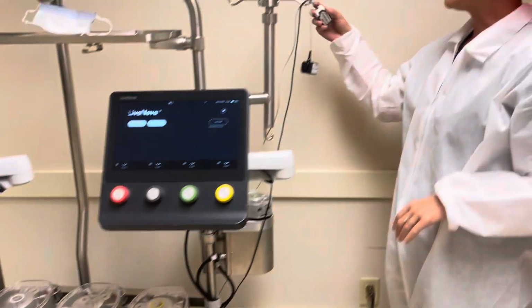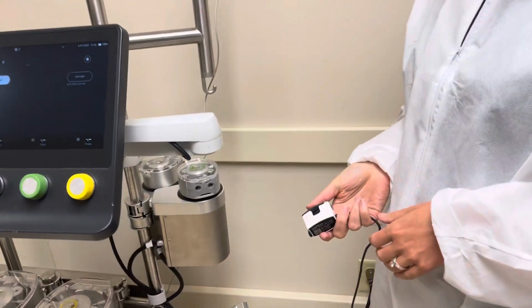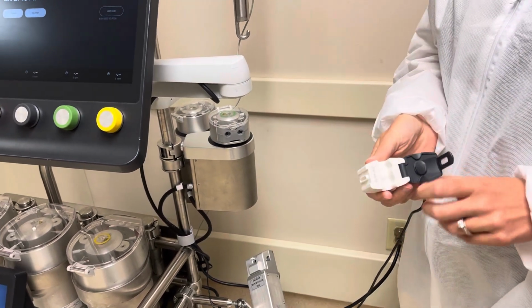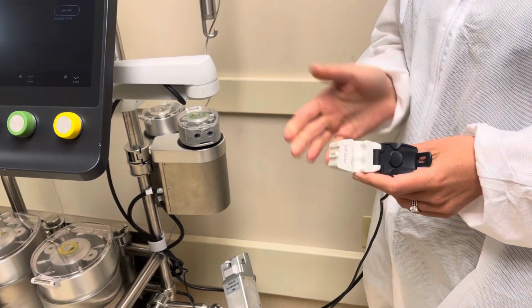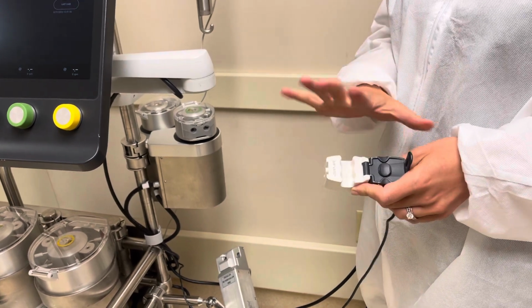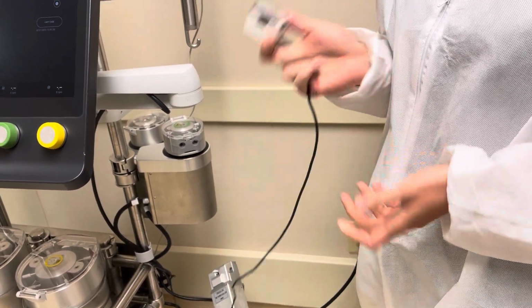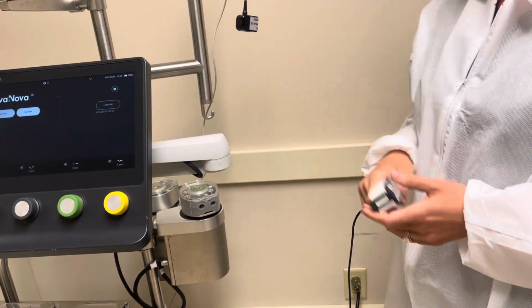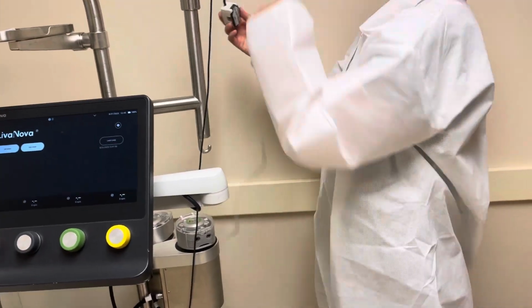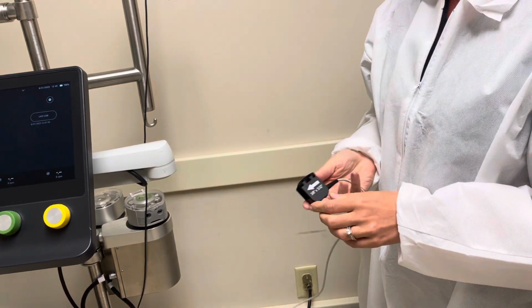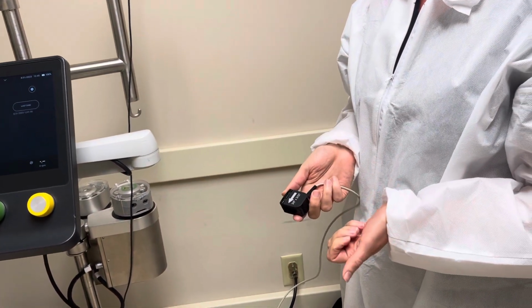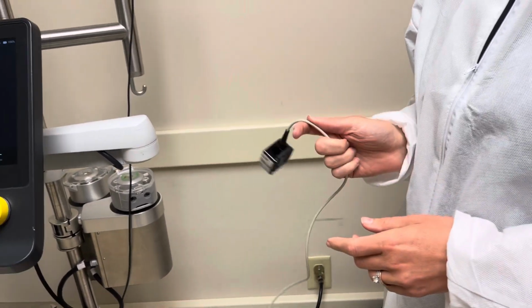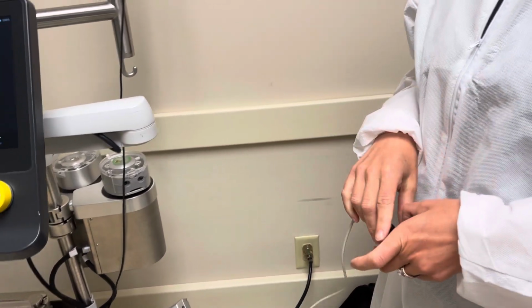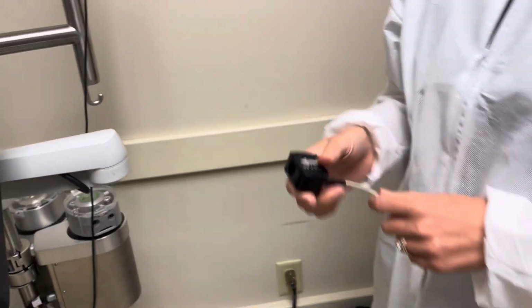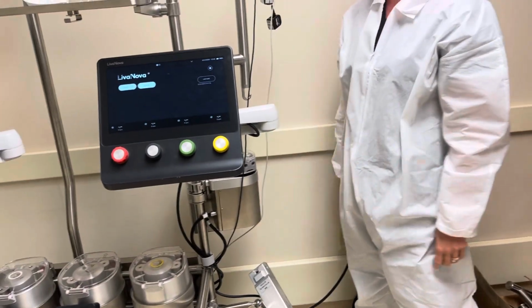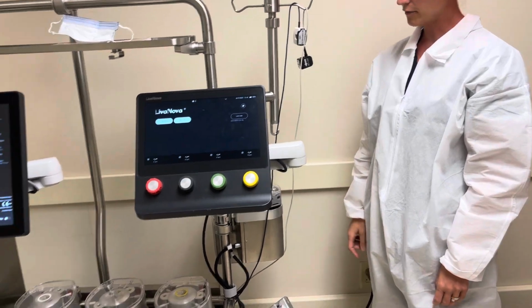A couple other improvements. Your bubble detectors now will clip right on the line. You'll notice there's not a bunch of padding and junk inside of them, so hopefully this will not wear out as quickly. It's super easy to clean. We have a variety of sizes with the bubble detectors. They're nice and lightweight. Your flow sensors: we've added a 1/4 inch flow probe now. We have a 3/16, and you can measure up to 3 flows now on this. But you have to have independent flow probes. Correct. Okay. Yep. And you have to have a separate flow module that would go under the machine for each one.